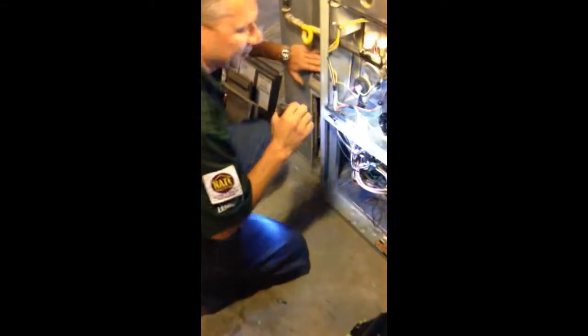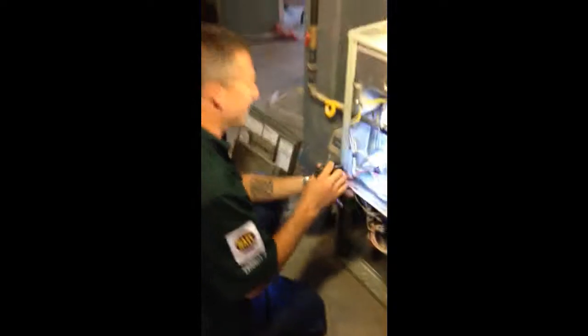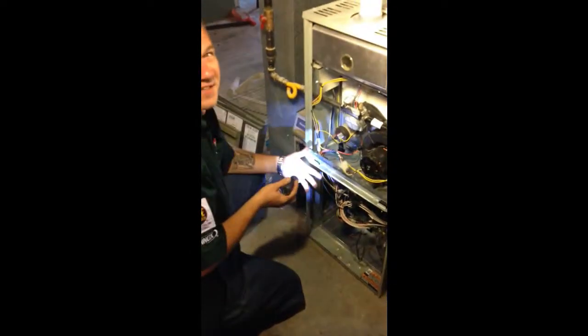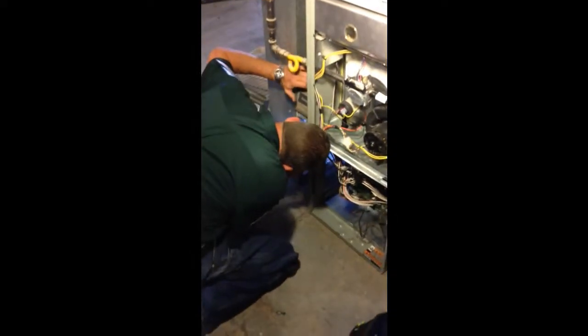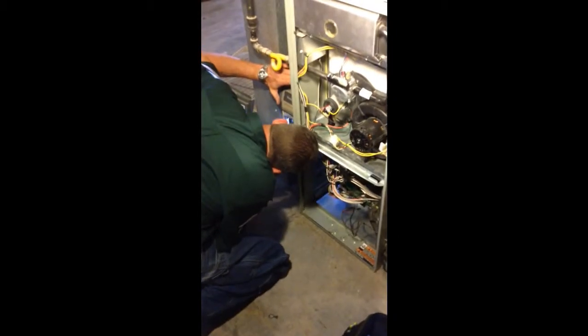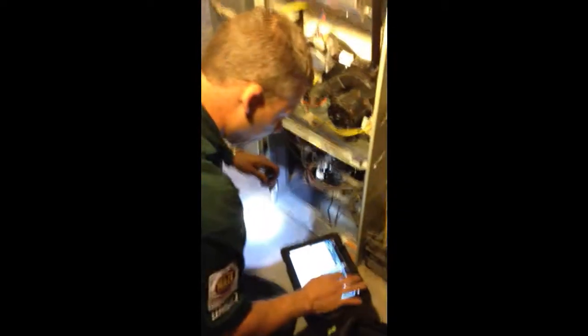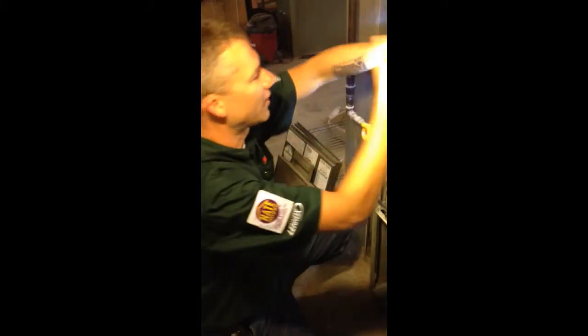And you brought a vacuum to do that, right? Correct. Also, this needs to be cleaned. I like to leave it cleaner than I found it. Doesn't look like you did anything if you don't clean it. Exactly. And yeah, they could probably use a duct cleaning, so that's something I'm probably going to recommend when I'm finished. So on my checklist, I'm going to write yes, the ducts are dirty. Usually we recommend a duct clean every 3 to 5 years. In this situation, it's probably closer to 3, because they have multiple cats.